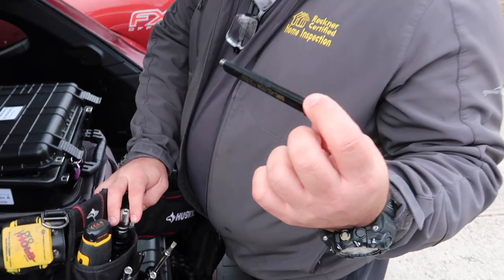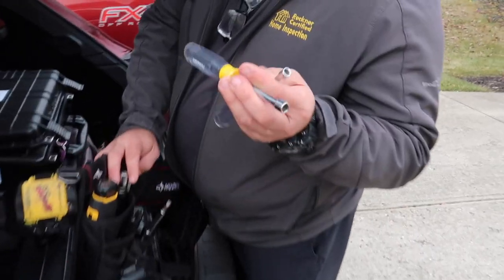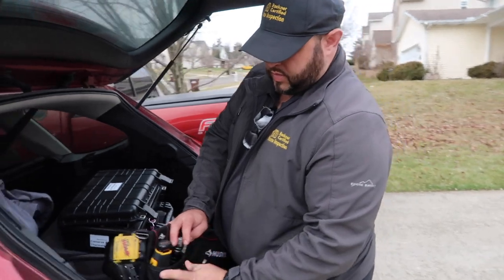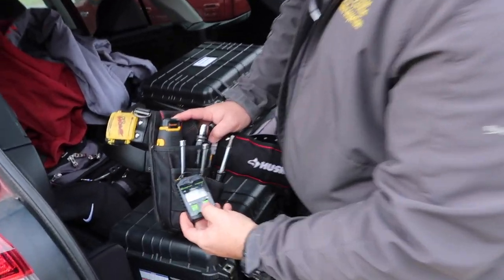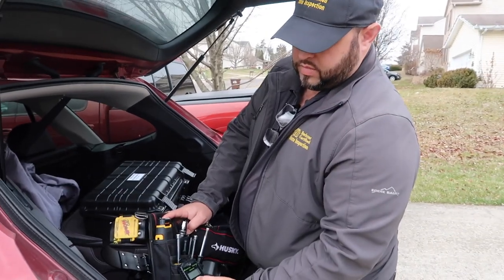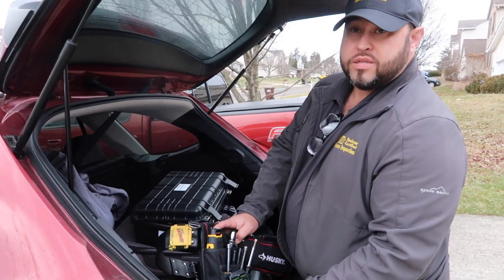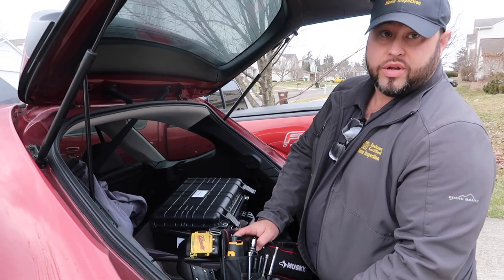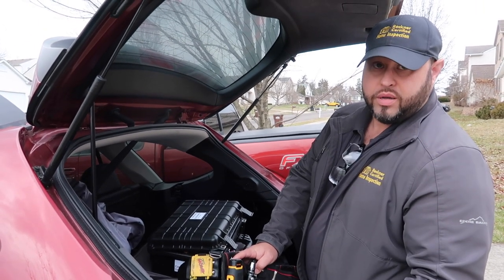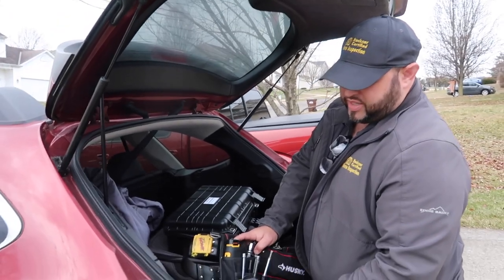He carries smoke pens for testing water heaters. He also has 5/16ths and quarter-inch nut drivers to get covers off furnaces, plus another screwdriver. He carries a Sensorcon carbon monoxide detector on his belt. You just turn it on and walk around with it — it beeps lightly in the 100–200 parts per million range, and gets louder and faster if you're really in trouble.